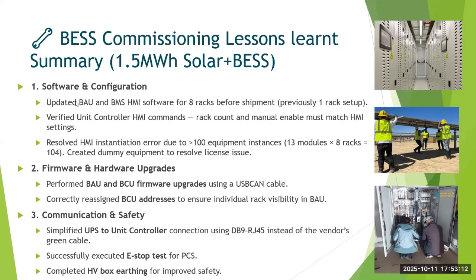So these were some of the challenges I faced in the software and configuration, predominantly on the battery management system side. And also the firmware and hardware for BMS, as I discussed earlier, BMS has a 3-layer architecture. One is the battery administrator unit BAU, and then we have the battery controller unit BCU, which is at a rack level. Then we have a BMU, which is at a module level. And predominantly the firmware we are going to upgrade will be at the rack level BMS and at the common BAU at a system level. So those addresses and also the configuration of those BAU, BCU, BMU at BAU level, because we'll have 8 racks and the system controller BIU has to know which rack is which address.